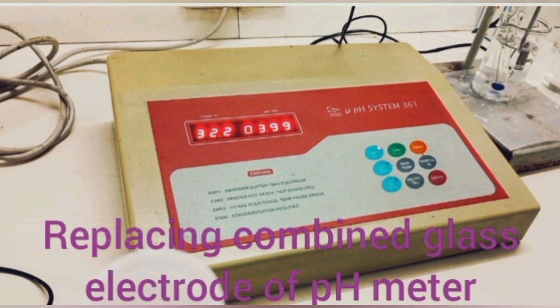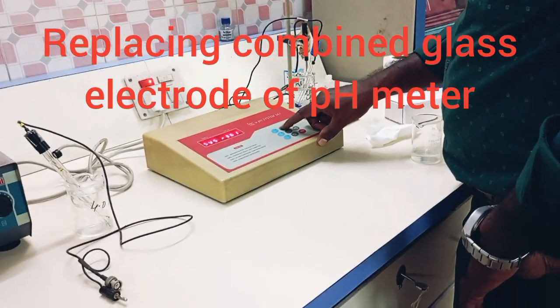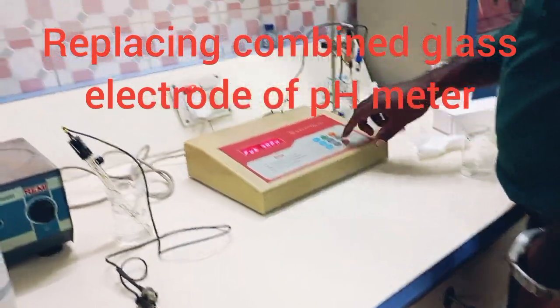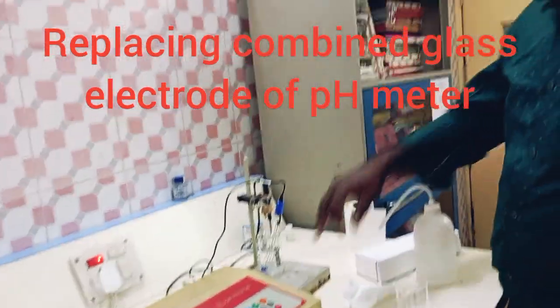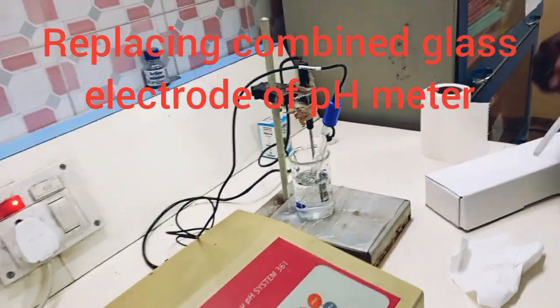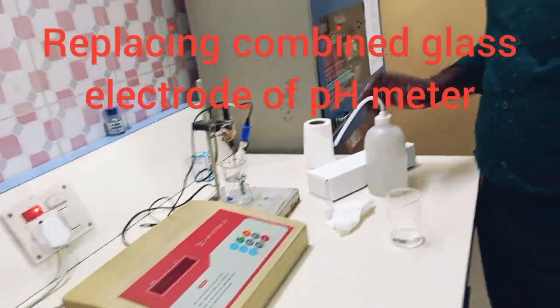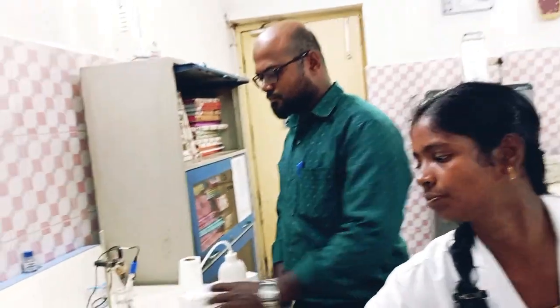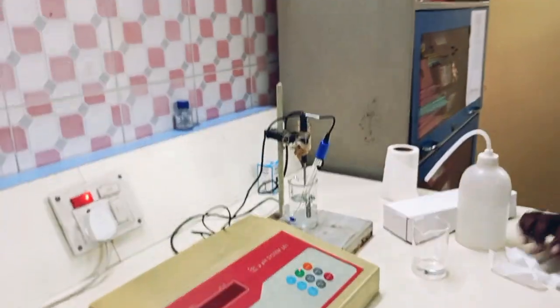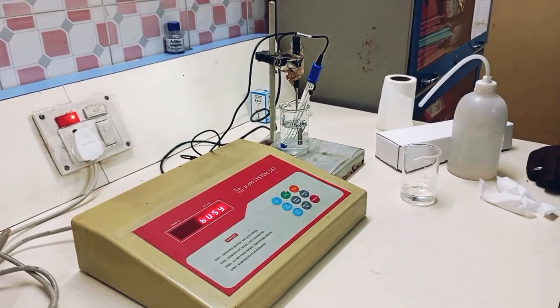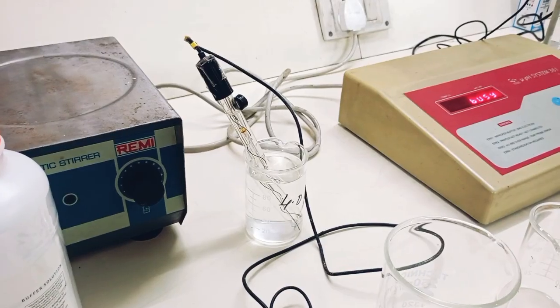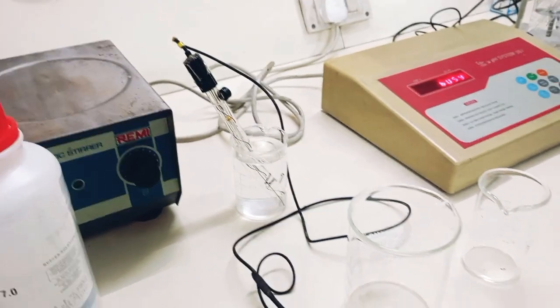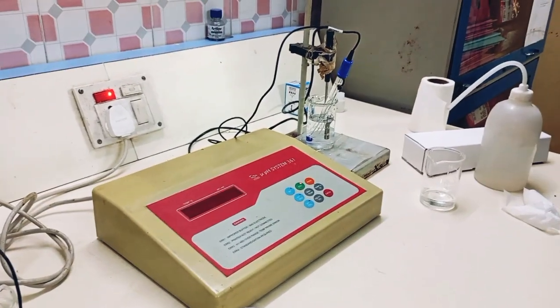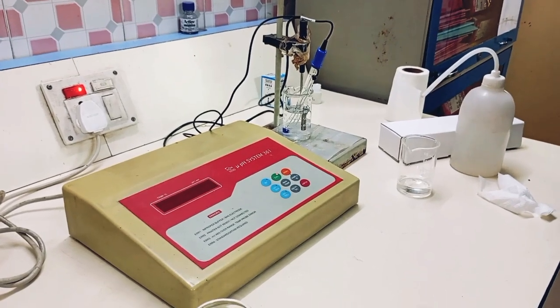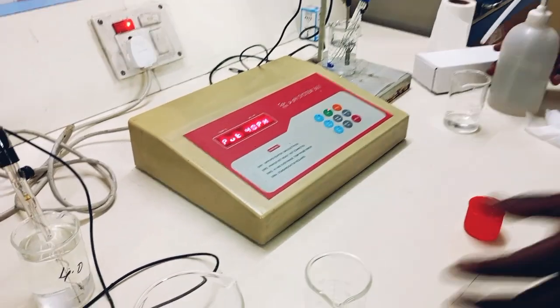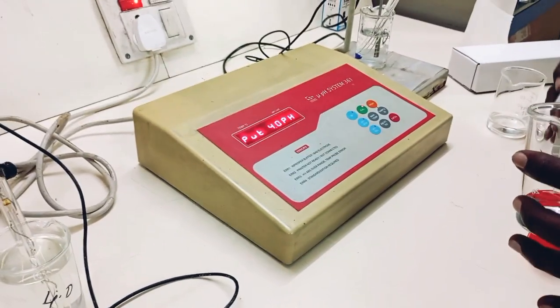Let us start. You see what we do now. First we will check this machine properly, connect it with this power plug, put it in any solution and press the pH reading to find out any problem. The machine itself indicates error 1, error 2, error 3, error 4 like that. If it is error 1, it means bad electrode or bad buffer solution. If it is 2, your printer is not connected properly. If it is 3, calibration is required again, and if it is 4, change the buffer solution.